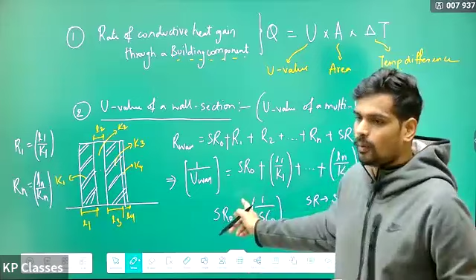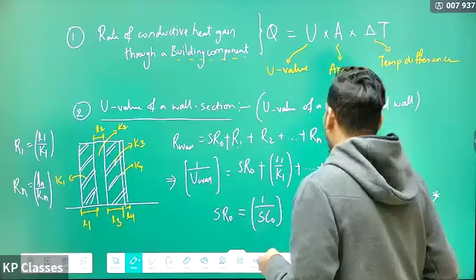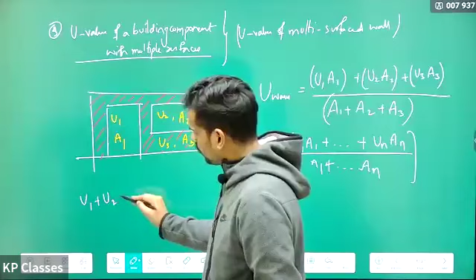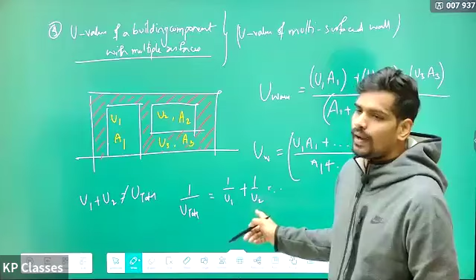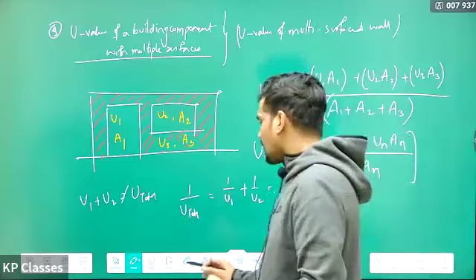So basically, what is R again here? R1, R2, R3, all these are the reciprocals of U values. So remember, U value is not directly additive in nature. Let me also write that here. U1 plus U2 will not give you the overall total U value. What will give you the overall U value is reciprocals of it. 1 upon U total is equal to 1 upon U1 plus 1 upon U2 plus so on, whatever layers you're having. The reciprocals of U value are additive in nature because reciprocals of U value are called resistance, R value. Right, so that's a quick revision of the U value based concepts.